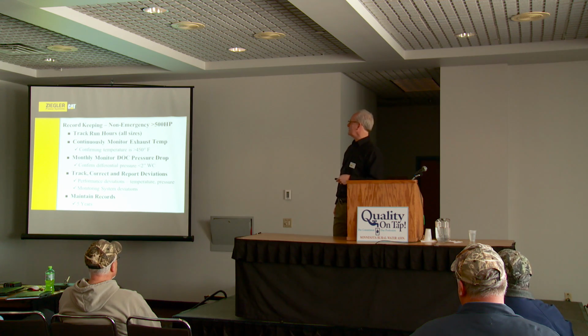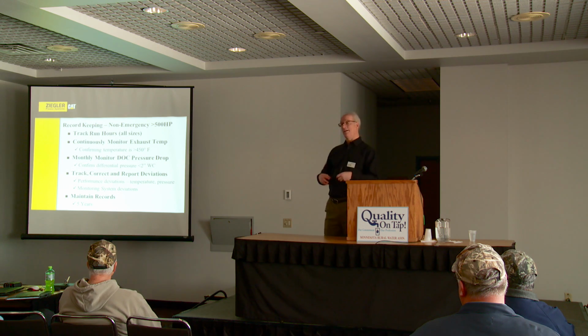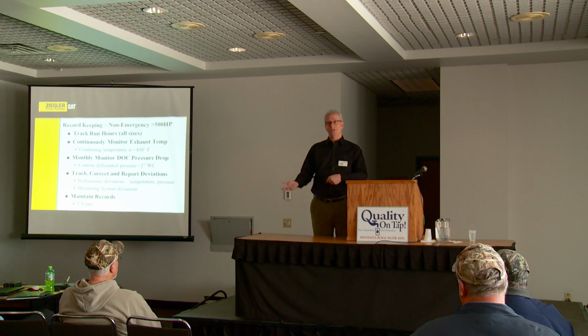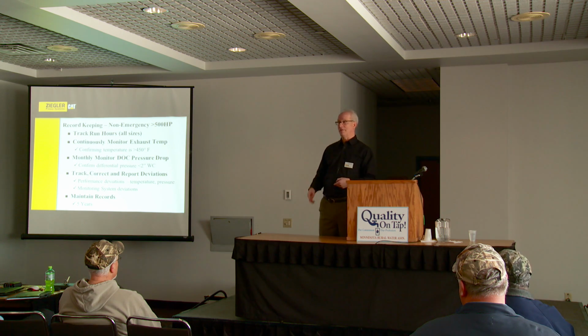And then, almost finally, on record keeping, you would need to track hours, but also these things have monitoring systems. For greater than 500 horsepower, a monitoring system continuously monitors temperature and pressure. And if you ever see an error from those things, the temperature or pressure has gone out of range, then you need to go figure out what's wrong, fix it, and note it as part of your record-keeping process.